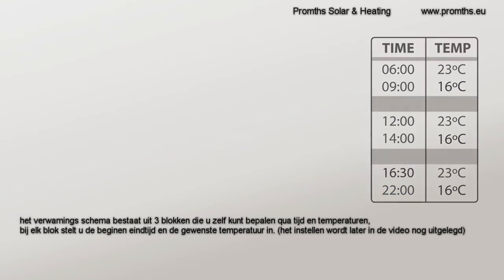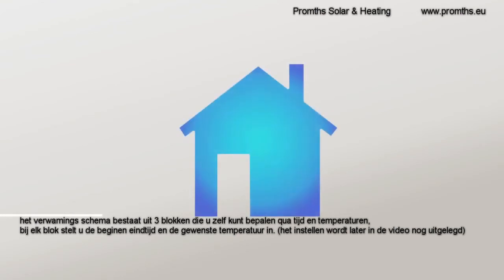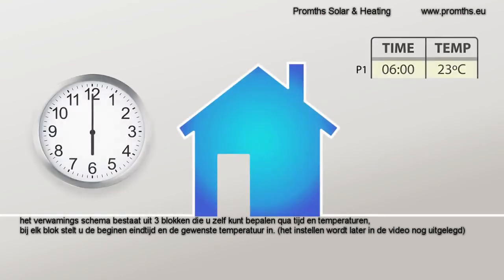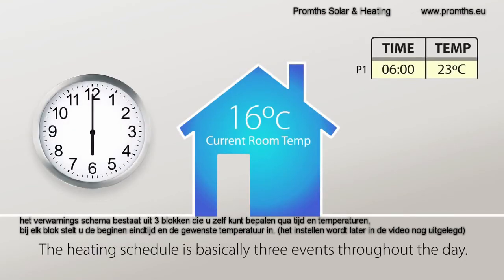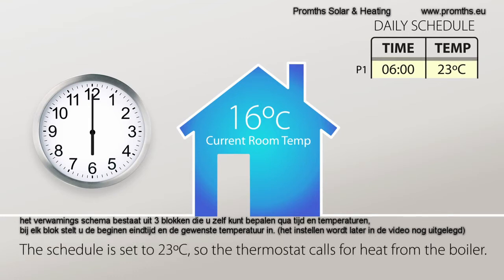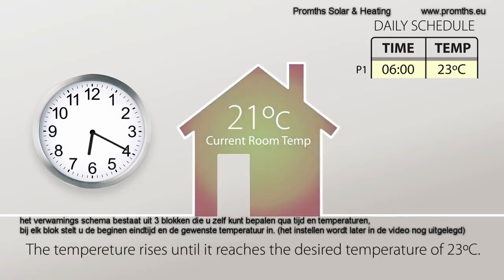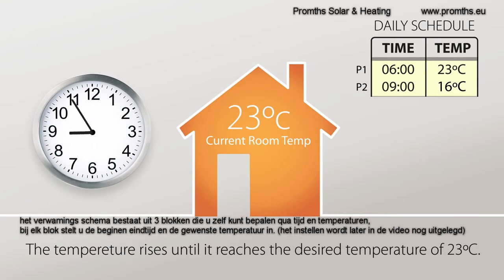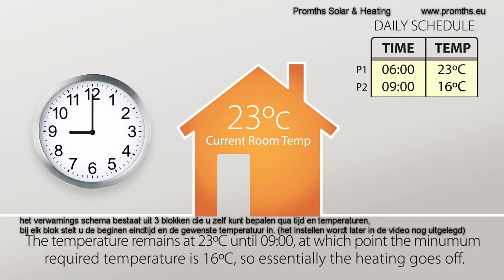At 6 a.m. the current room temperature is 16 degrees. Program 1 is the first on time and temperature. The temperature is set to 23 degrees, so the thermostat calls for heat from the boiler. The temperature rises until it reaches 23 degrees. Program 2 is the off time and temperature. At 9 a.m. the minimum temperature required is 16 degrees, so essentially the heating goes off.